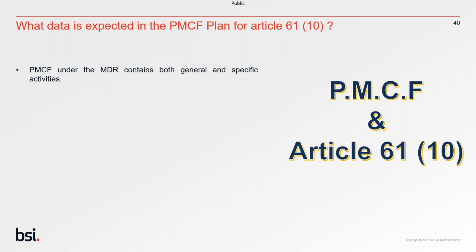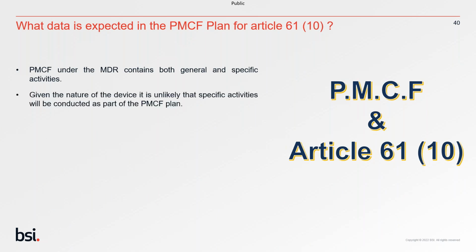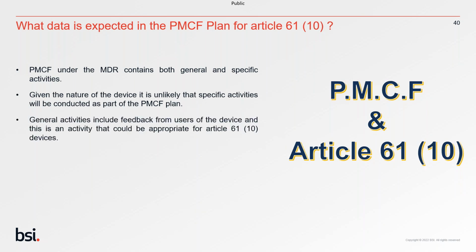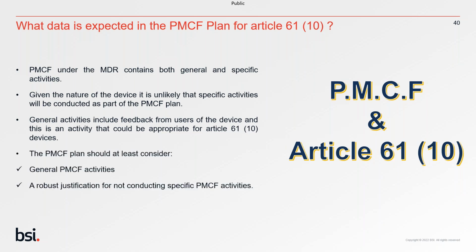So PMCF under the MDR contains both general and specific activities. Given the nature of the device, it's unlikely that specific activities will be conducted as part of the PMCF plan. General activities include feedback from users of the device, and this is an activity that could be appropriate for Article 61(10) devices. Under the MDR, PMCF doesn't mean a post-market study. It means both general and specific activities, which includes how you are going to get feedback from users of the device. So typically for these devices, we do expect a PMCF plan that considers the general PMCF activities mentioned in Annex XIV, Part B, and also a robust justification for not conducting specific PMCF activities.